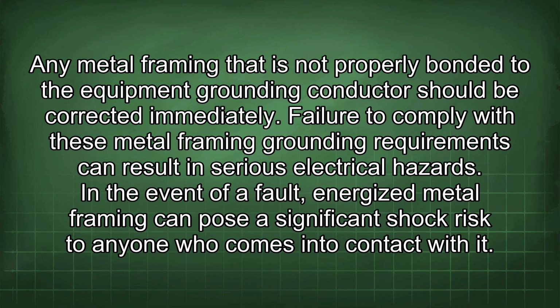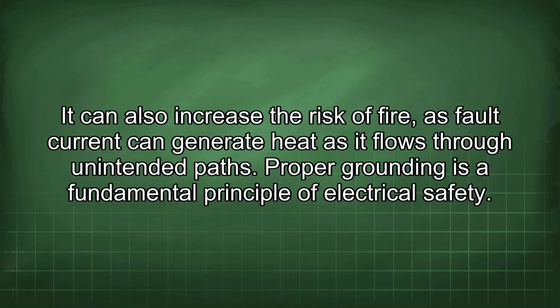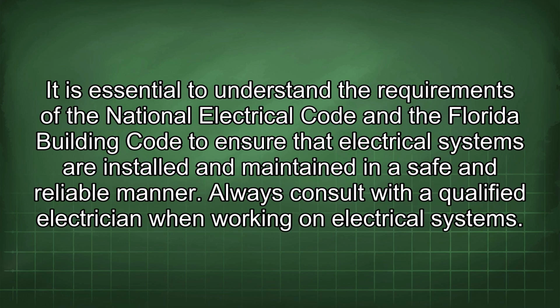Failure to comply with these metal framing grounding requirements can result in serious electrical hazards. In the event of a fault, energized metal framing can pose a significant shock risk to anyone who comes into contact with it. It can also increase the risk of fire, as fault current can generate heat as it flows through unintended paths. Proper grounding is a fundamental principle of electrical safety. It is essential to understand the requirements of the National Electrical Code and the Florida Building Code to ensure that electrical systems are installed and maintained in a safe and reliable manner.